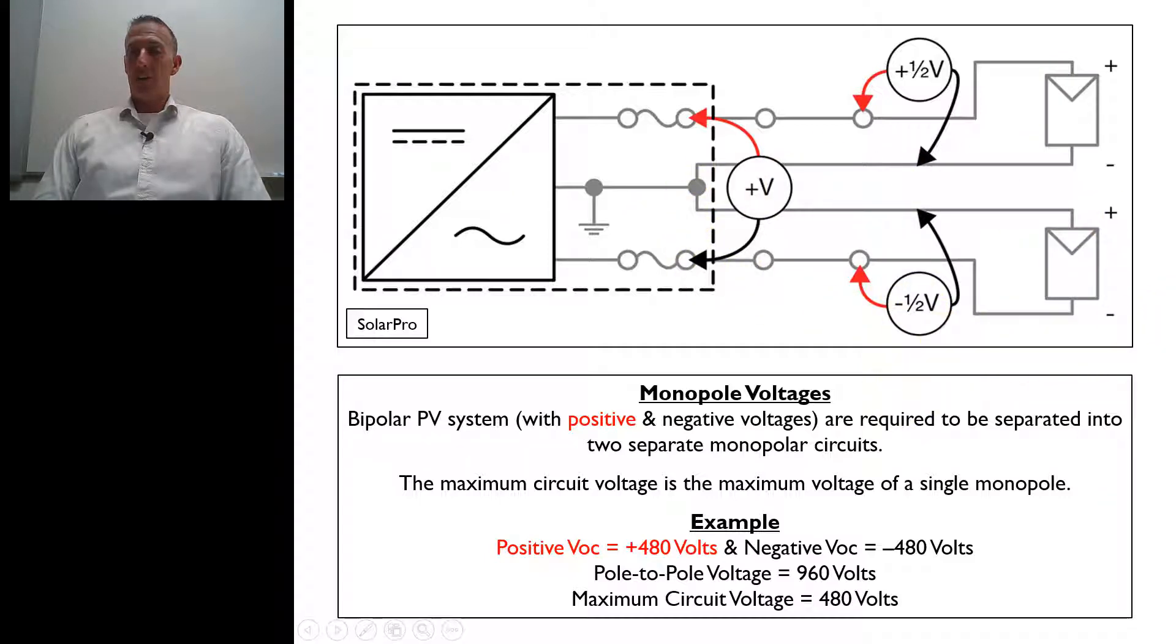But when we're talking about the NEC, the 2017 NEC and the maximum voltage requirements, the maximum circuit voltage is going to be 480 volts, and that would be based on either this monopole or this monopole here.